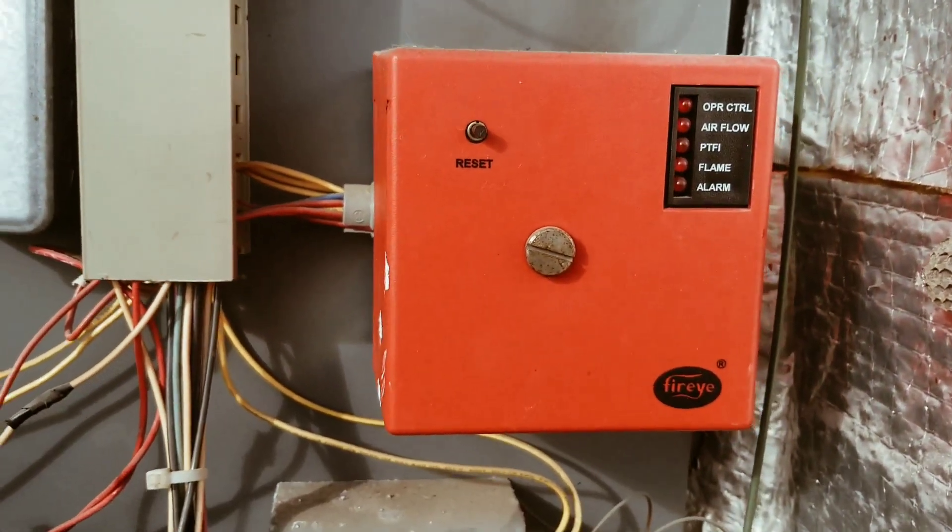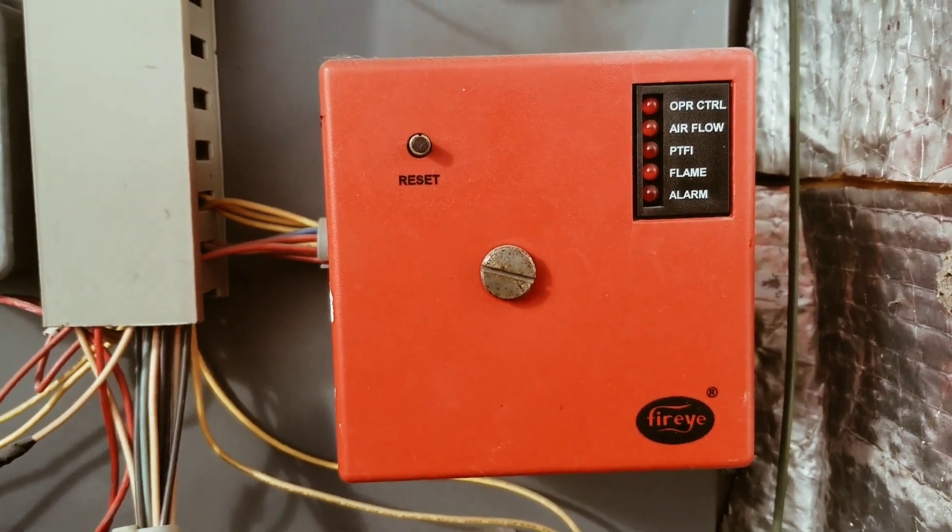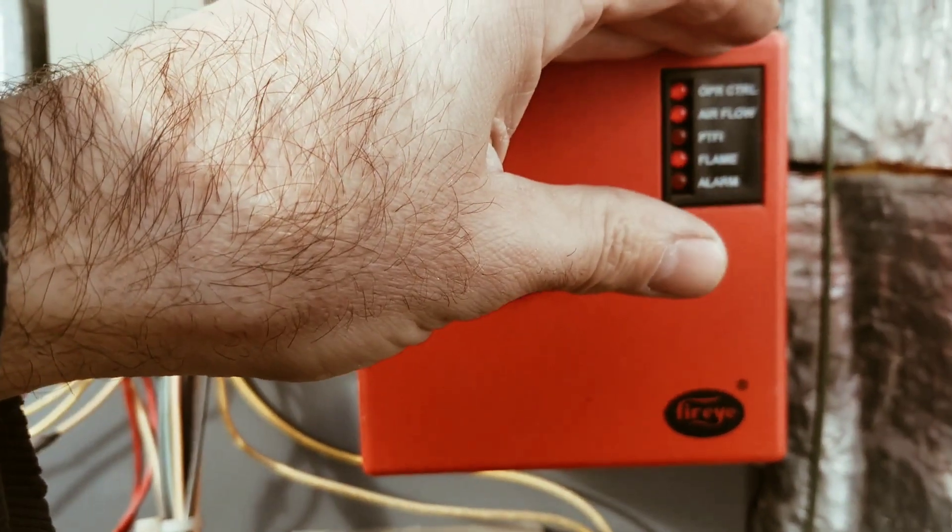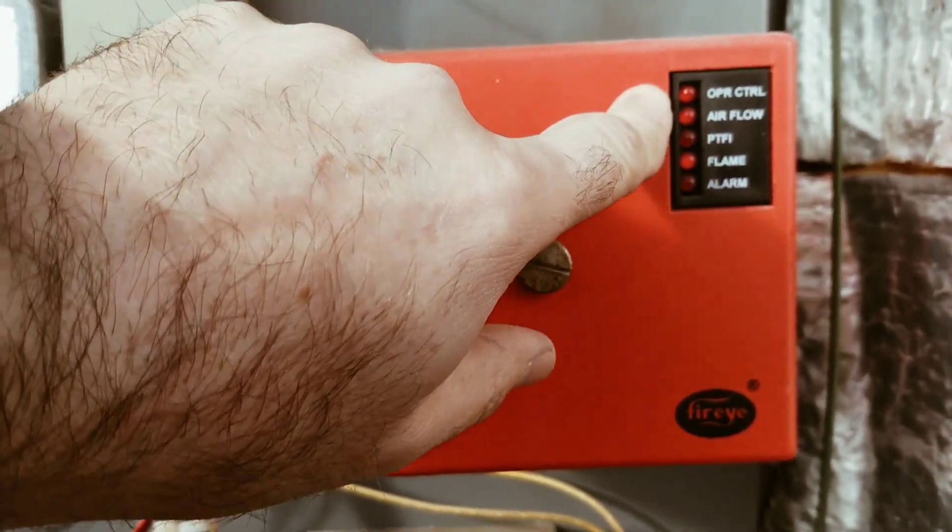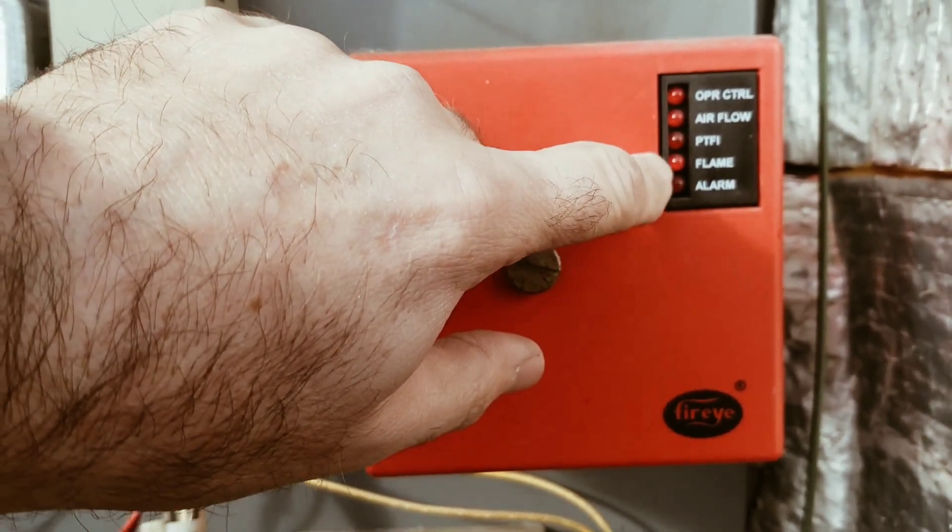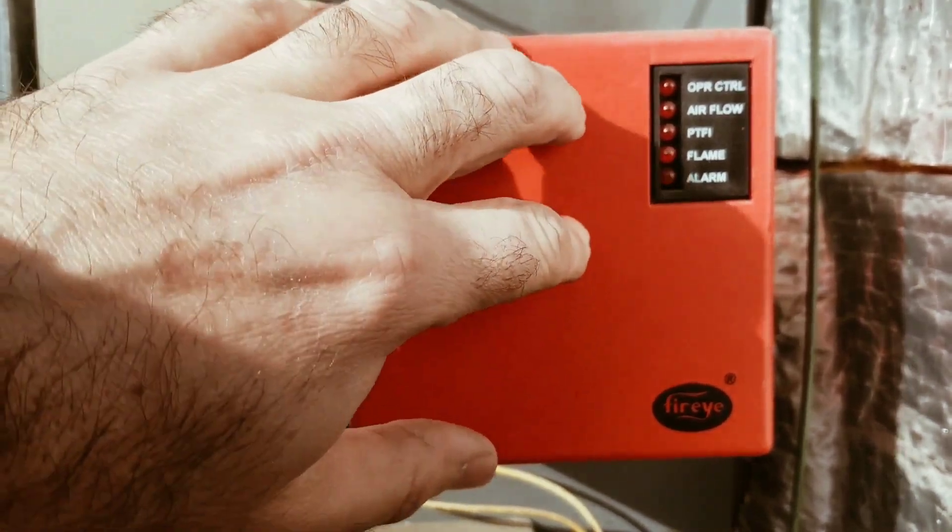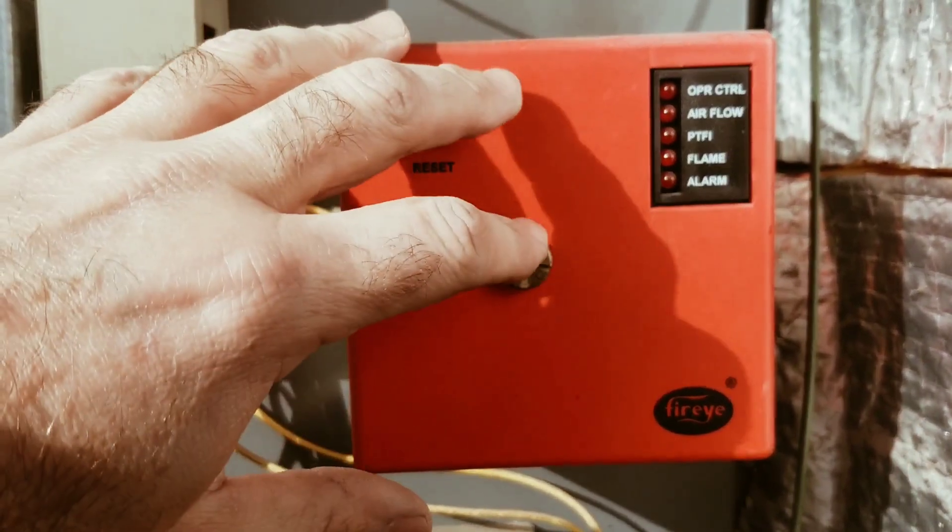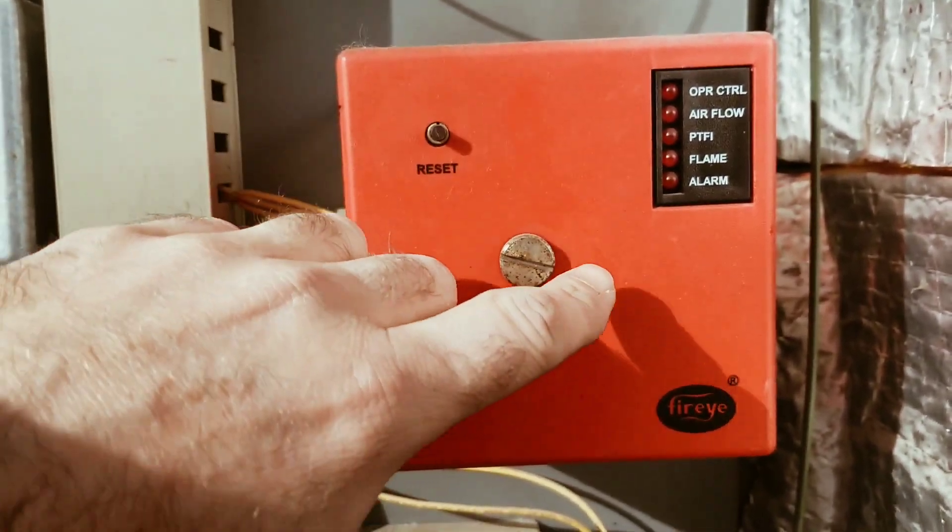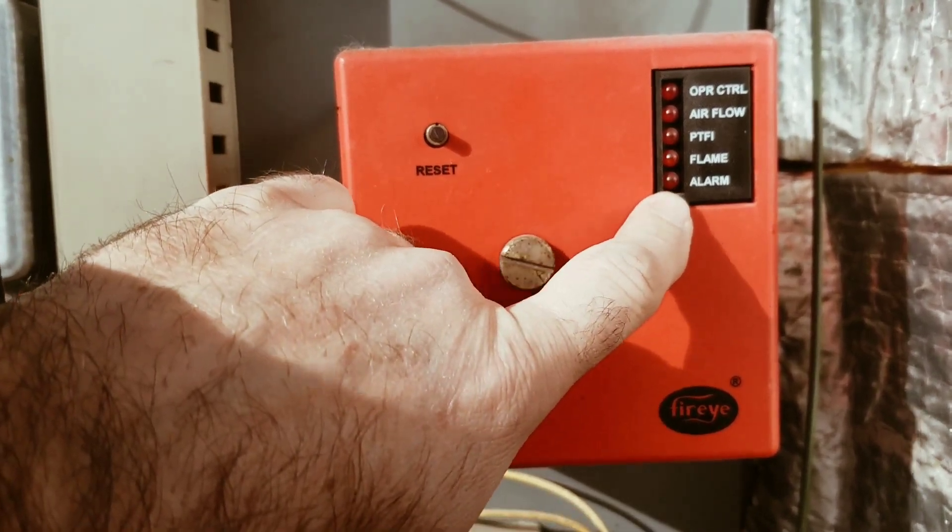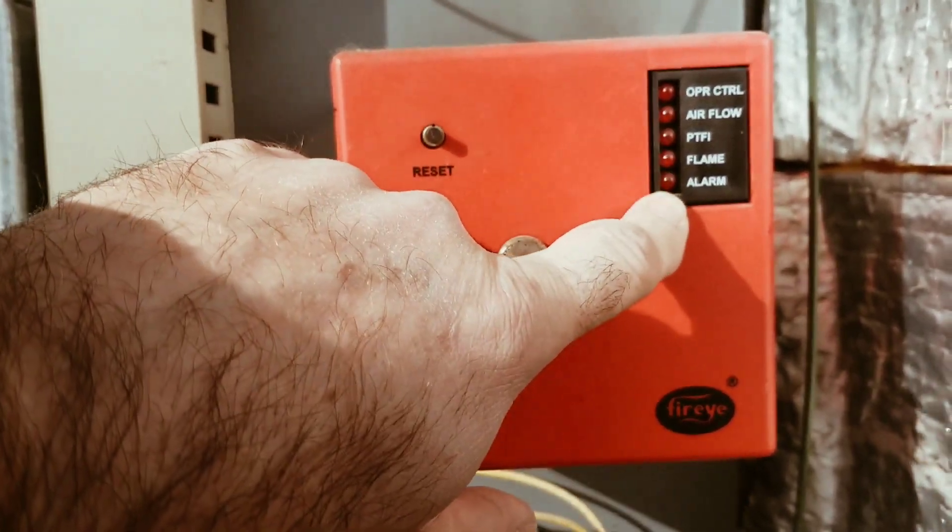Here we have our FireEye burner control. We have some lights on it now. The operating control, air flow and flame. If we were to shut the gas off and just tried to fire and we couldn't have the flame rectification take place with the flame rod, it would lock itself out and this alarm light would come on.